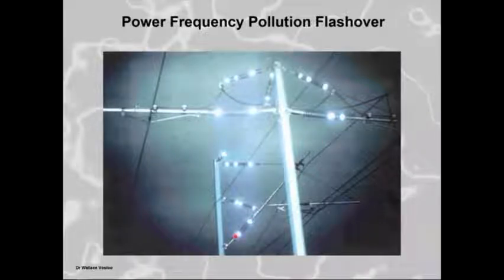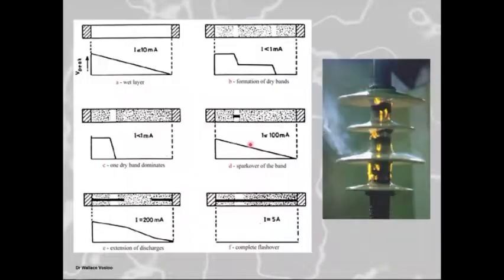Now, normally when there's more than a third of the insulator that has got discharge activity on it, you're living on a short thread. So when a quarter of the insulator has got discharge activity on it, you would say, ooh, I must start doing something. But when there's a third of that insulator that's got discharge activity like this on it, then you start worrying and you need to do something very quickly.